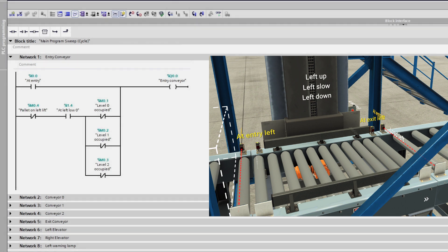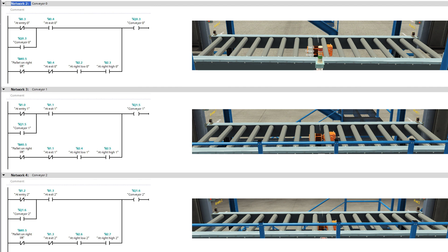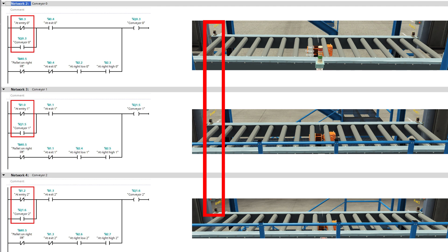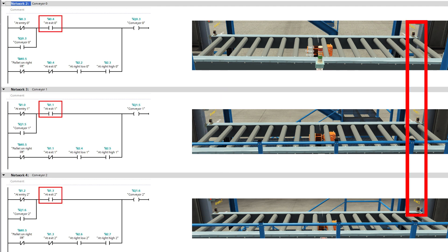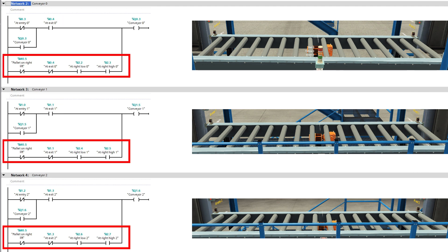In my main block I made the programming for all the conveyors and stack lights. For the entry conveyor, it should always run until it blocks the at-entry sensor, or when the lift doesn't have a pallet and none of the levels are occupied — using the signals sent from the function block. It also ensures the lift is at level 0 using the at-left-low sensor. For the conveyors at the three different levels, they latch when the at-entry sensors get blocked and unlatch once the pallet reaches the at-exit sensors. They restart once the lift reaches the respective level and there are no pallets on the right lift.